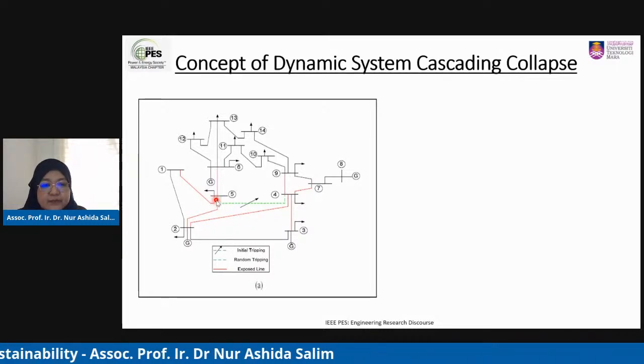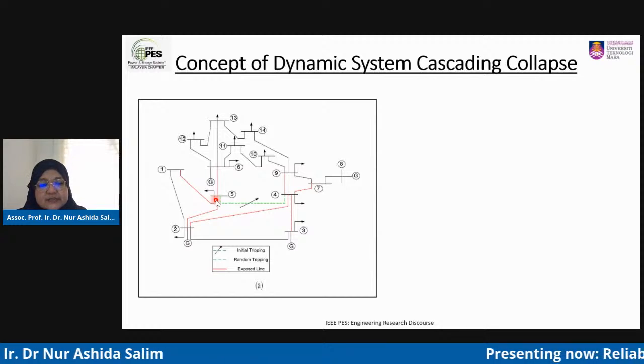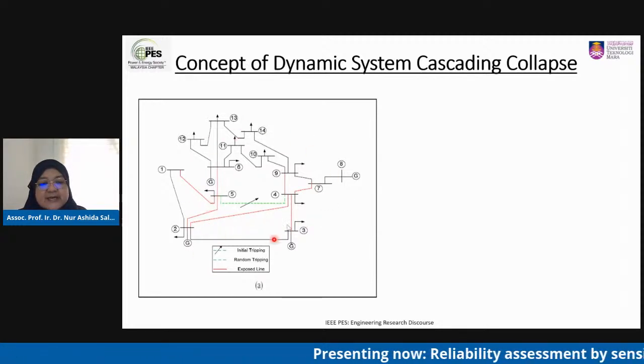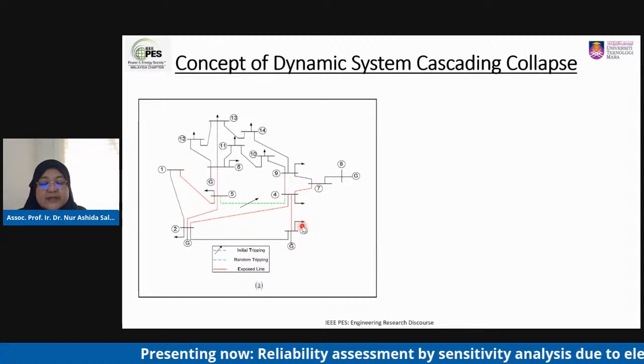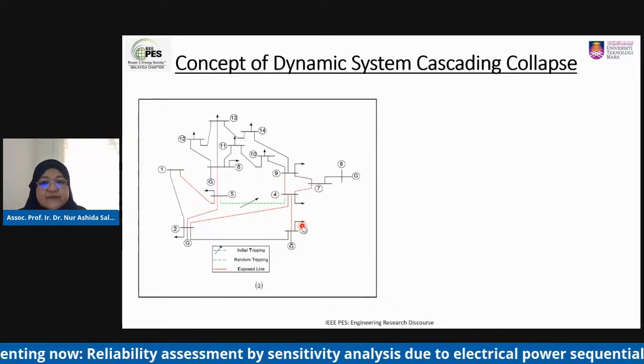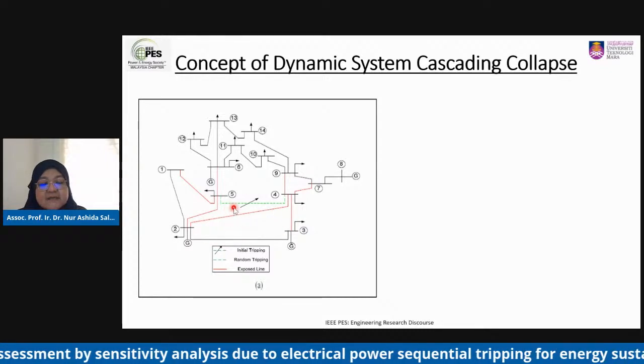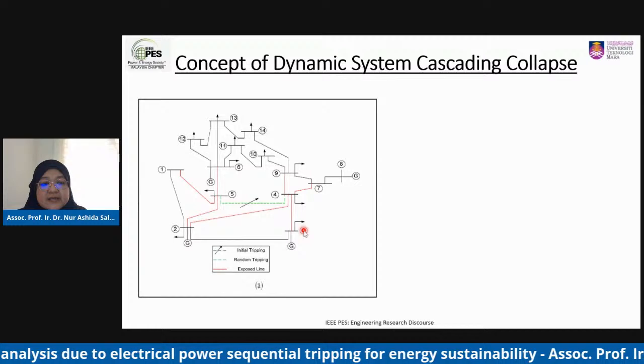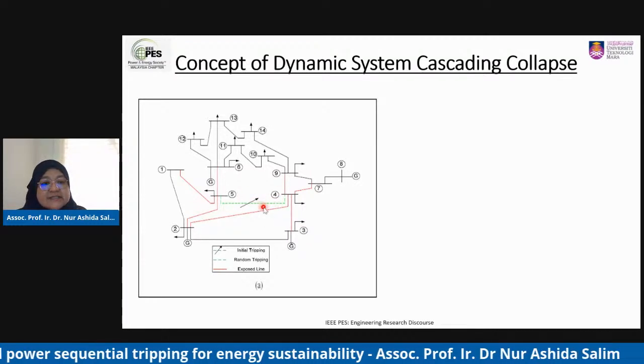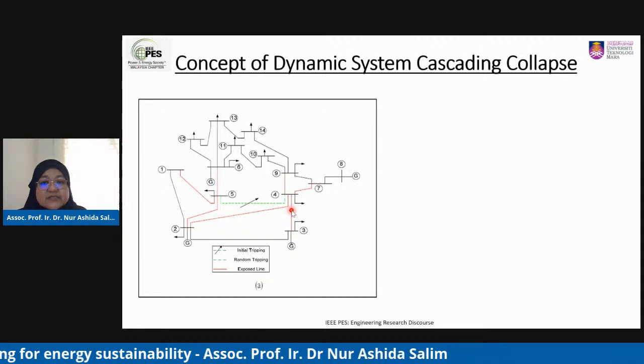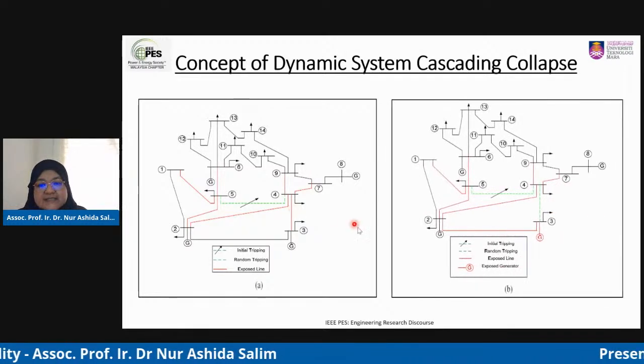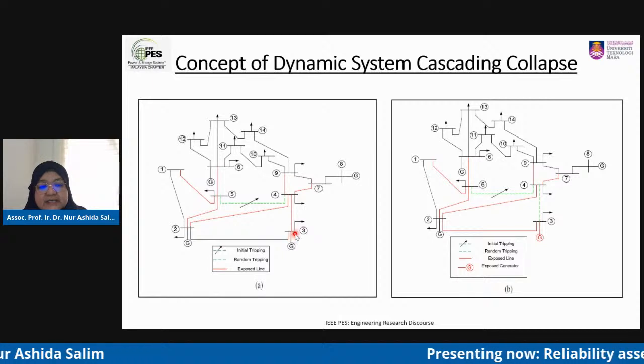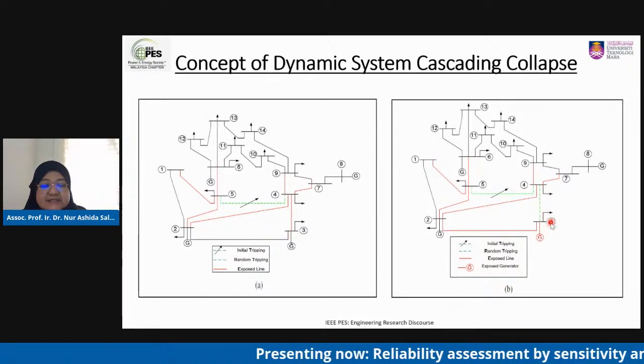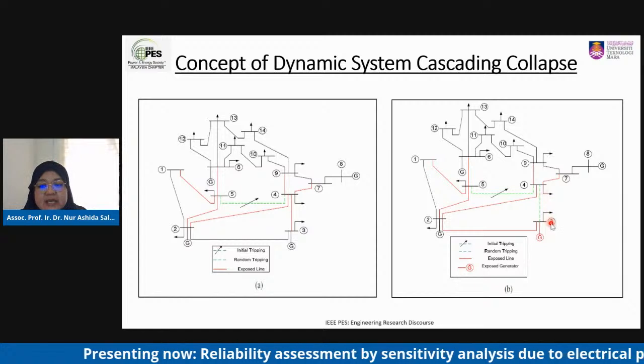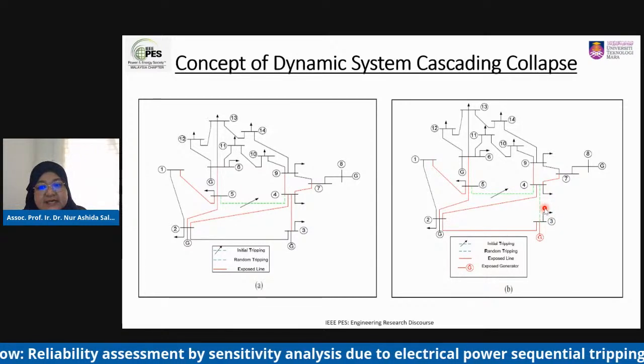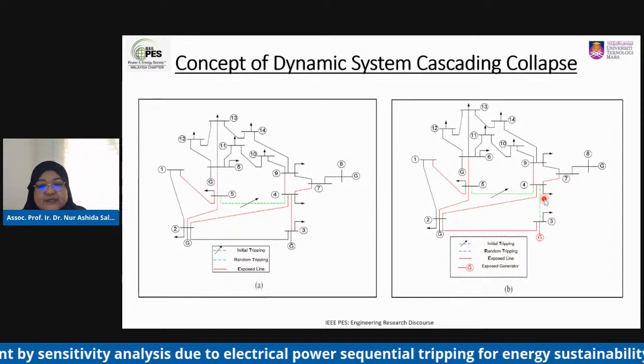All right, so again, we have to perform the power flow solution to look at whether the thermal limit of these exposed lines has been violated or not. If the thermal limit is still within the acceptable range of the line, then no exposed line will trip next. But let's say line 4, 3 violates the thermal limit, which is the MVA rating. So this particular line will be the next line to trip. So this is the second transmission line tripping.